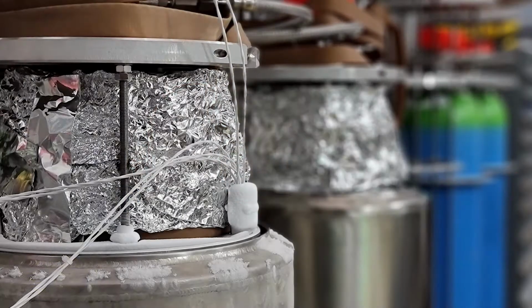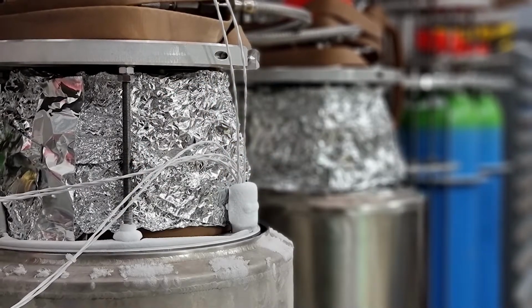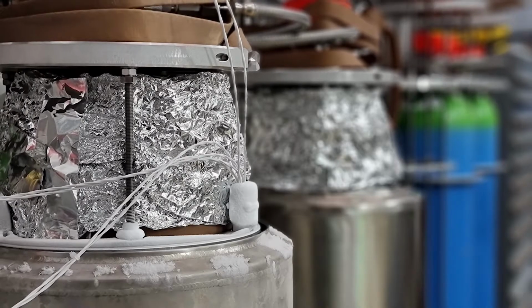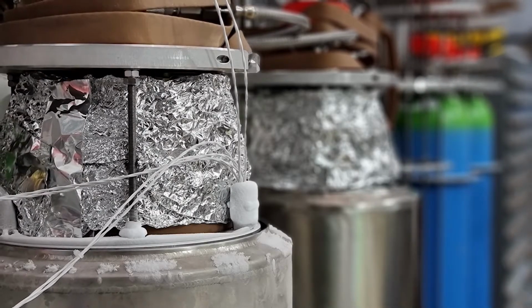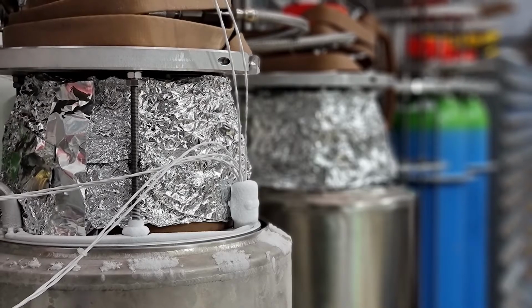The last purpose of the gas handling system is to perform pressure-dependent automatic recuperation. If, for any reason, the pressure inside the cryostat or at any place in the gas handling system was to exceed the safe operational value, check valves would open and direct some gas to a gas cylinder in the storage array, which is always kept frozen. The system allows us to safely and automatically reduce the pressure in the cryostat without loss of xenon. In the event that the pressure relief to the bottle is not sufficient and that the pressure increases uncontrollably, a pressure relief valve can open and vent gas to the atmosphere to prevent the burst of any part of the system.